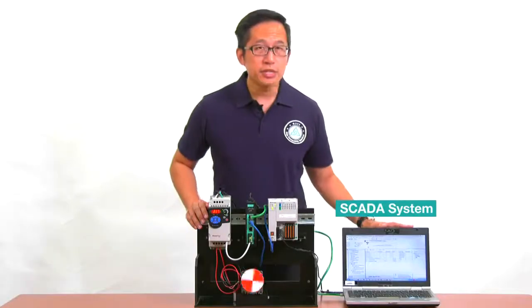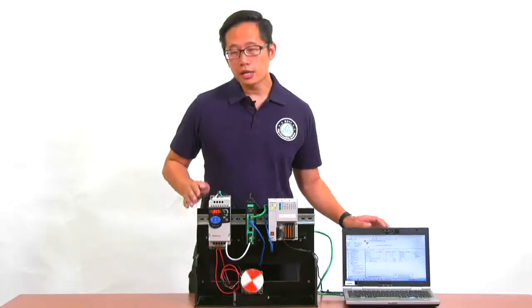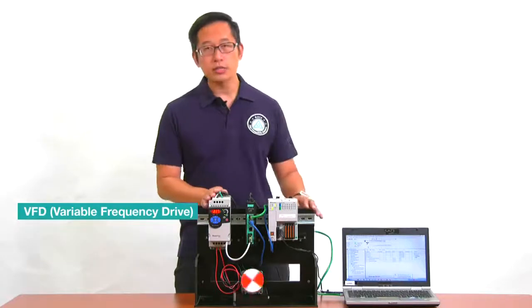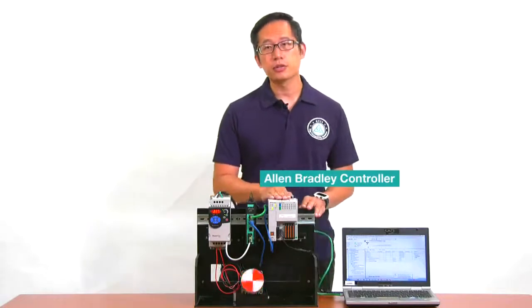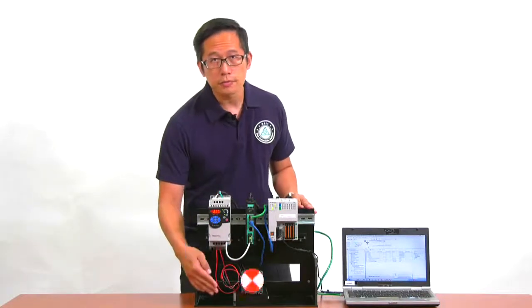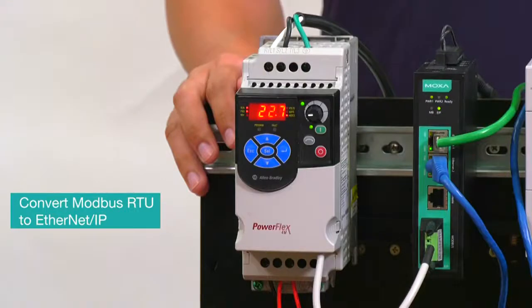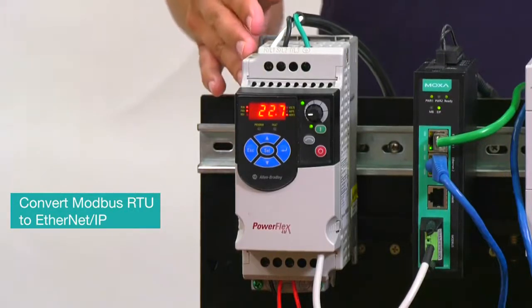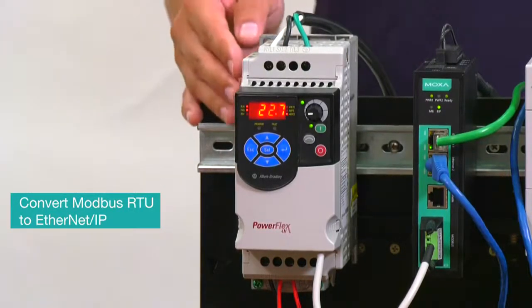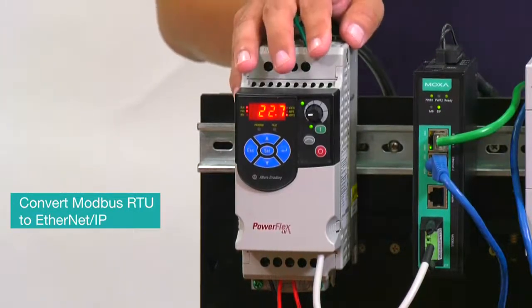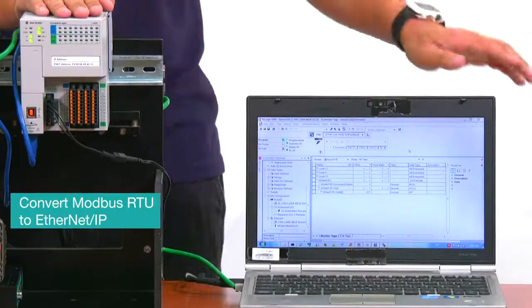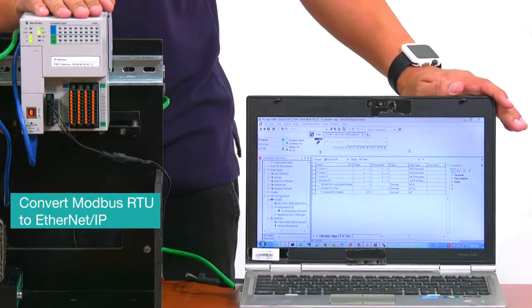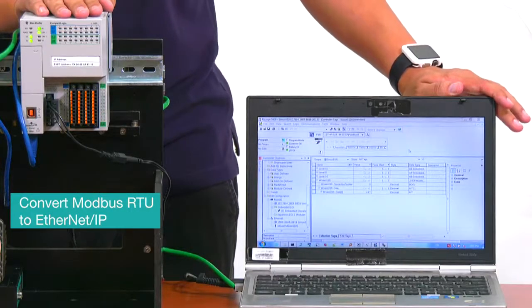Here, we have a PC with SCADA software installed, and a VFD that's connected to an Ethernet IP controller to control the speed of this motor. Now, to connect this VFD to your control network, you need to convert Modbus RTU protocol, which the VFD uses, to Ethernet IP protocol, which the controller and the SCADA system use.